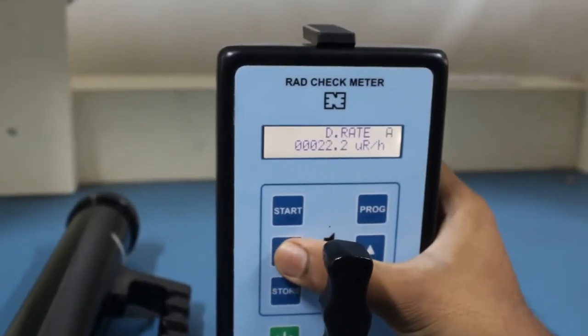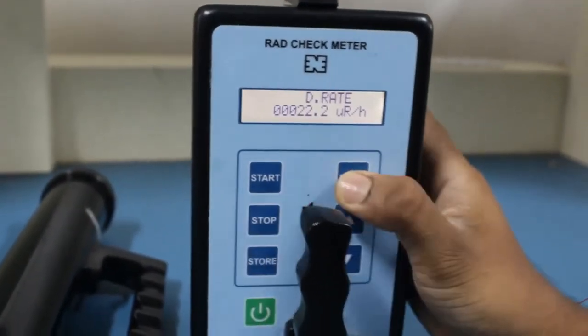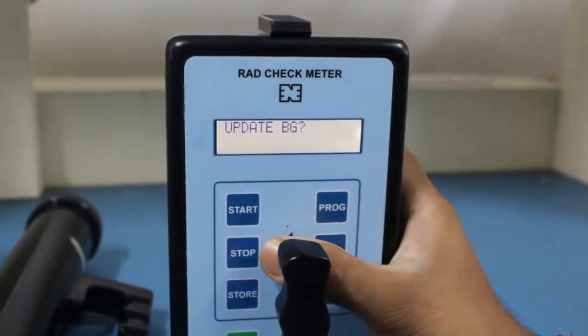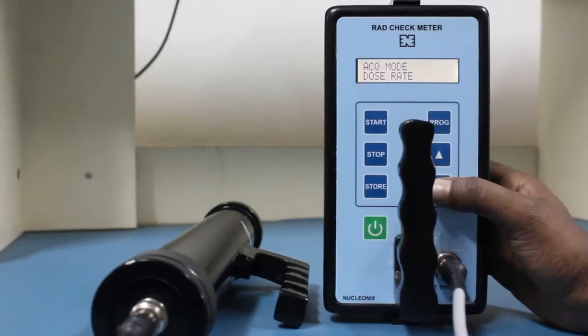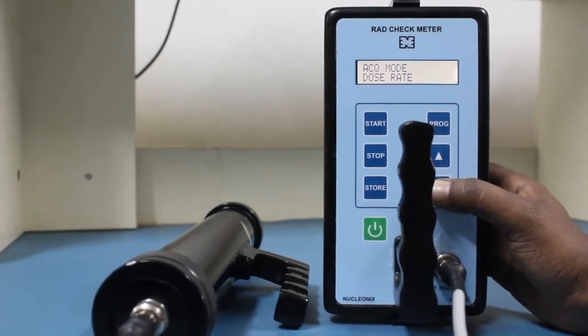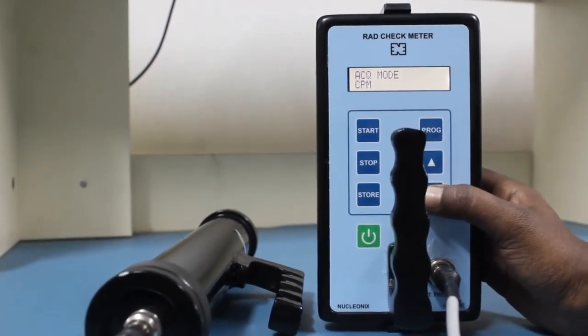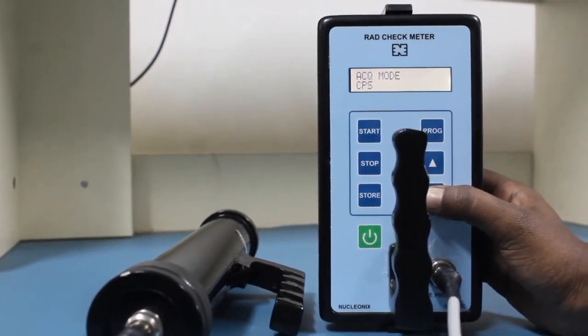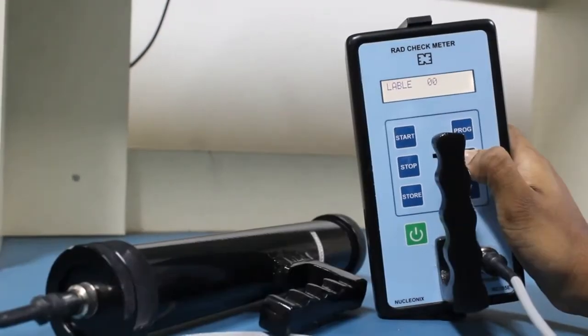Going to the interface of the RadCheck Meter, press stop button and then press PROG button. In the ACQ mode, you can select different modes of operation like dose rate mode, preset time, counts per minute CPM, counts per second CPS.